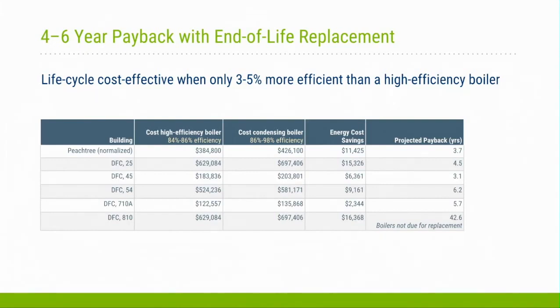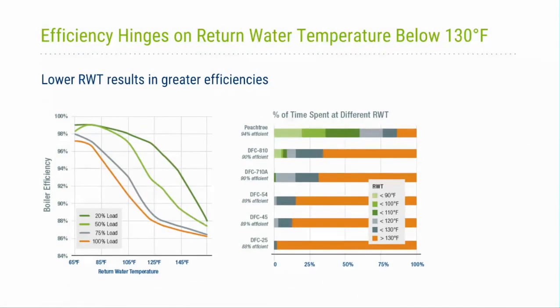Next slide. There's a lot going on in this slide, so I'll hit on it pretty quickly. We'll start with the graph on the left, and really this whole slide is looking at the efficiency of the condensing boilers. The title says it all. It hinges on getting return water temperature below 130 degrees F. Why that's important is that's where the flue gases start condensing and you really get the efficiency bumps. And so you see in the graph on the left, you've got boiler efficiency on the y-axis relative to return water temperature.